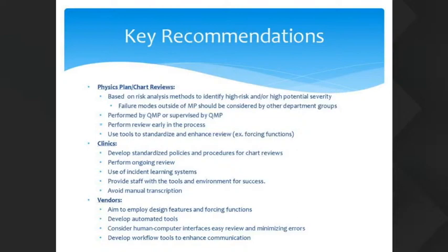As we've already discussed, these plan reviews should be performed by a QMP or closely supervised by a QMP, by the way. The definition is included in the report. Perform the review as early in the process as possible and use tools to standardize and enhance the review.